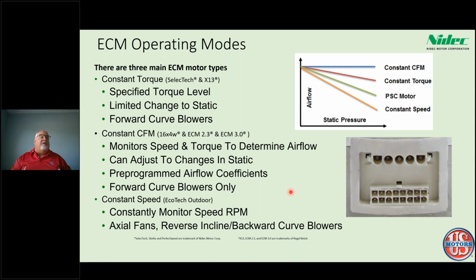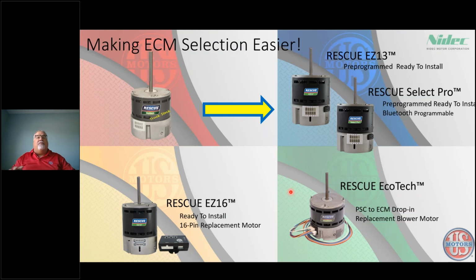Again, we have to do something to solve that, and we've done some things in the past where we've used different types of products. We've taken out ECMs and put in PSCs. Please try to avoid that as much as possible, because what you're doing is taking away all the bonus efficiency, the high efficiency that you get with an ECM product. I'll give you an example. A standard ECM is going to run in the high 70s to low 80s as far as efficiency goes. And when you're talking about a PSC, you're looking at 60 to 65% efficient. That difference in efficiency adds up over time to a lot of dollars. So just keep that in mind as you're making those decisions to replace. Please go back with an ECM product.